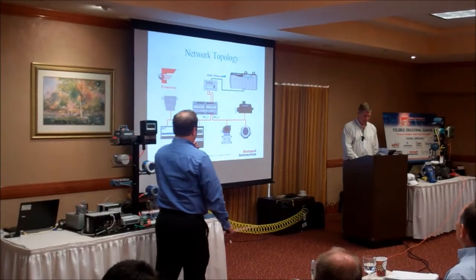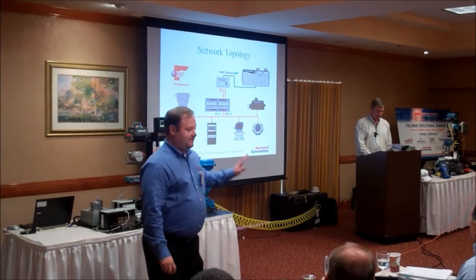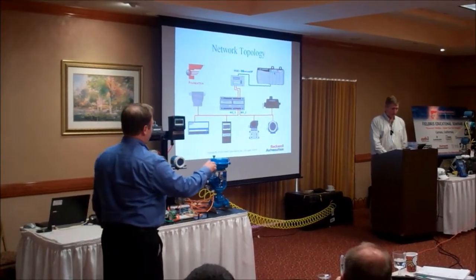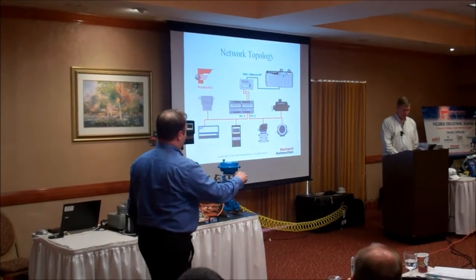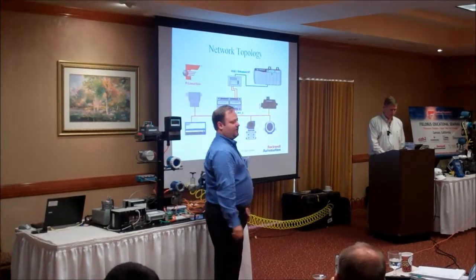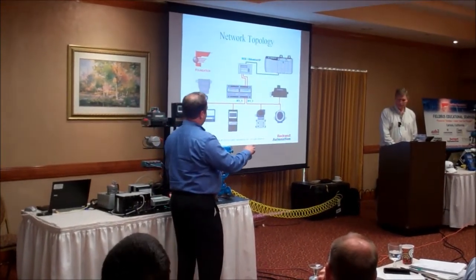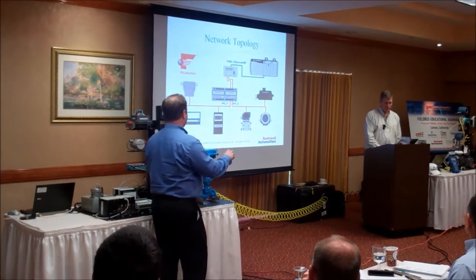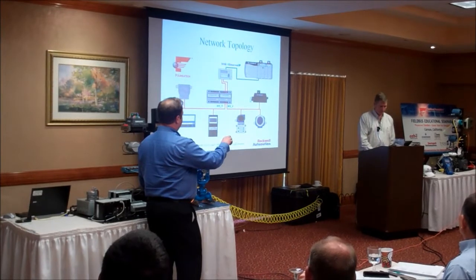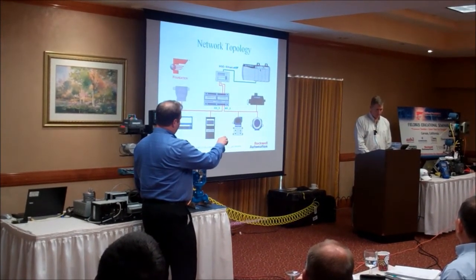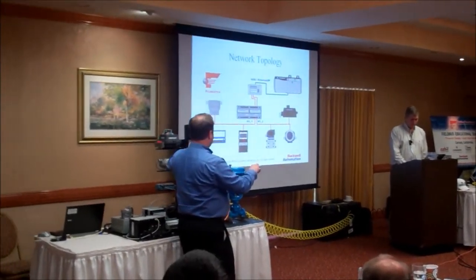What we have is a Rockwell system. Notice the controller here — the controller isn't really doing anything in this demo. Right now we are working with a host that actually goes through Ethernet, through HSE, to the FFLD, and then out to two separate H1 segments through my FFLD up here. This is a bridge — it's our FFLD linking device — and it's connected through HSE. This is the power supply. This is the FFLD, two lines, one through a power supply with an MTL diagnostic module.